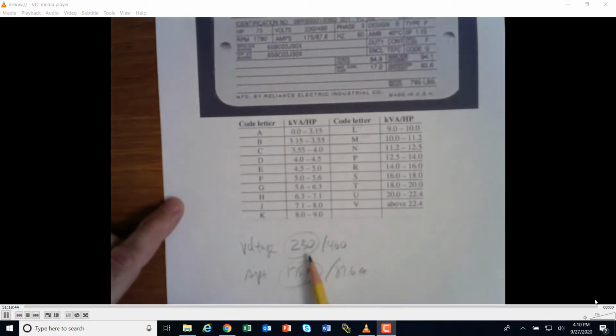So if we were looking, let's say, at the 230 volts, we could overduty this a little bit. We could take this 175 amps right here. Okay, let me get my calculator going, and we could take that and go 175 times 1.15, which is coming up to 201.25 amps. Okay, so that's called your service factor amps, where you might run a little bit over duty, and it is a continuous duty motor. All right, so it's a pretty big, hefty motor, and it'll run a little bit over the nameplate.